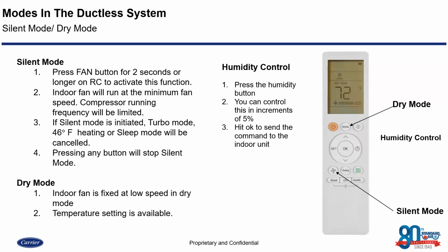So we're not passing air as quickly over that coil, so that we have more potential to remove more moisture from the space. Okay, now this kind of leads me into my next segue, which is humidity control. So now we have built-in relative humidity control for the space. We can choose a set point and set a particular percentage of humidity that we're trying to maintain, whether that be 50%, 55%, 45%, depending on the scenario.